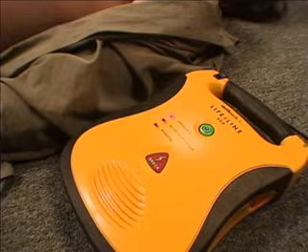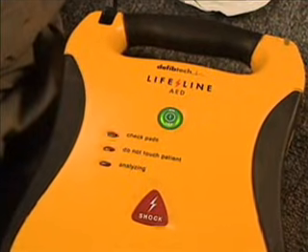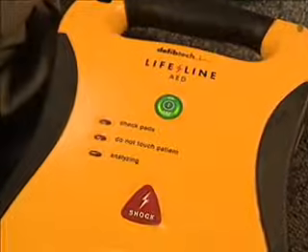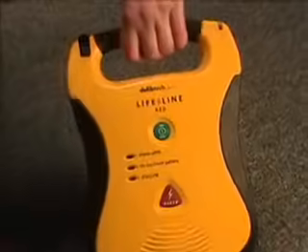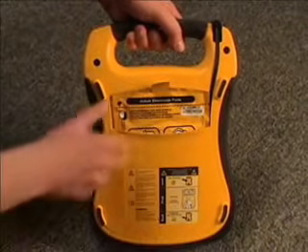Call for help. Remove pads from the package and back of the unit, and apply pads to the patient's bare chest as shown. The Lifeline AED should have been stored with the pads already pre-connected and in the pad storage pouch on the back of the unit.